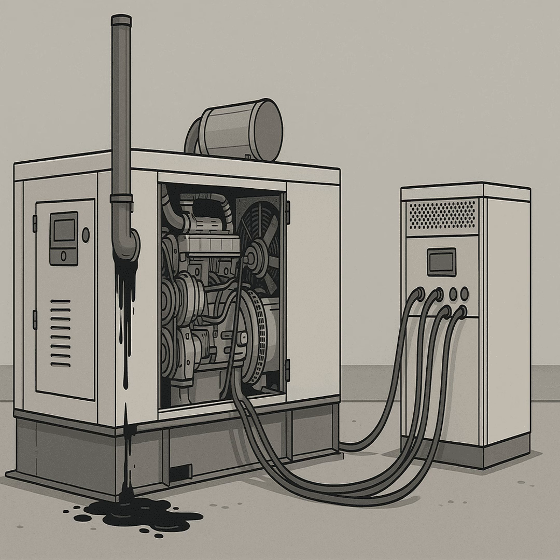But you still need some form of regular testing. Oh, absolutely. You still need to meet regulatory requirements like NFPA 110 in the US for emergency systems, which often mandates monthly exercise for 30 minutes, specifying either 30% of the rated load or running under conditions that achieve the manufacturer's minimum recommended exhaust gas temperature. So that annual load bank test becomes crucial for verifying capacity and cleaning things out.